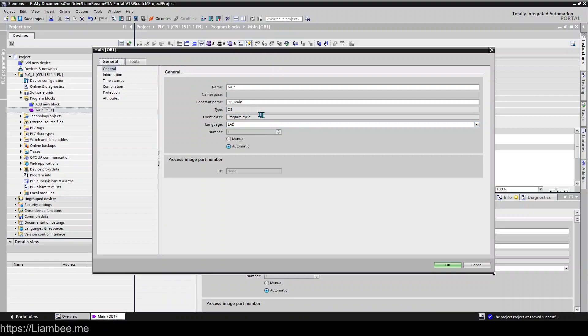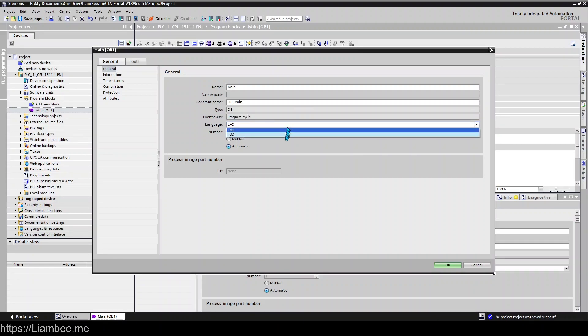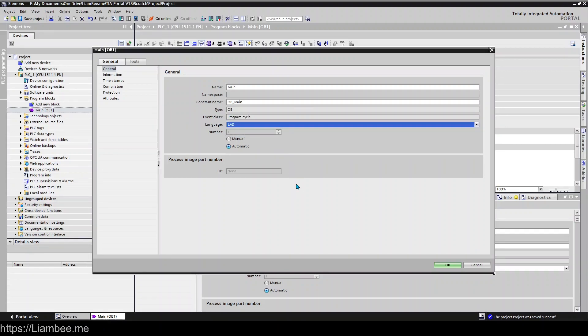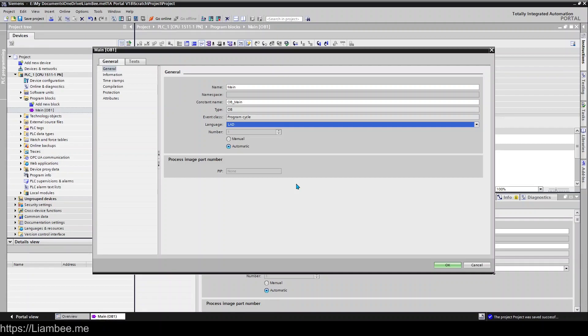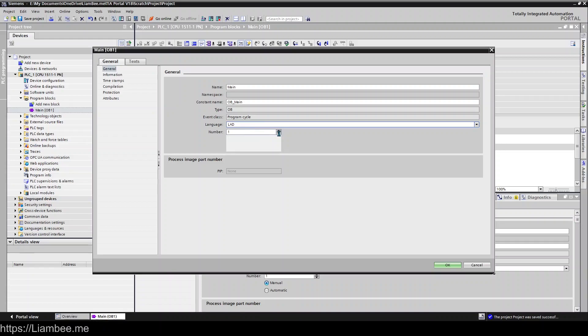Here you can rename the block, have a look at various other configurations. So you can see it's a type OB, it's in the Program Cycle event class, you can't change any of this stuff. You can change between Ladder and Function Block but you can't change between say Structured Text and then back to Ladder and Instruction Lists. So in previous Siemens systems you used to be able to change between Ladder, Function Block and Instruction List. You can't do that anymore because of how Siemens puts together Ladder. And also Instruction List is a deprecated language. Siemens still support it but by IEC standards it's deprecated.